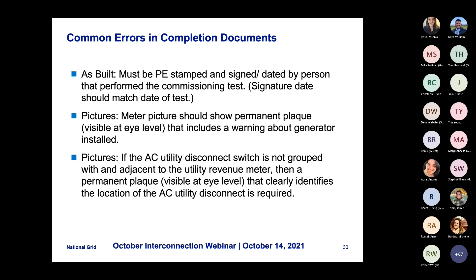For photos, we want to see a picture of the meter and showing the permanent plaque visible at eye level that includes a warning about the generator installed. Also for the AC utility disconnect switch, we want that labeled there. If it is not grouped and adjacent to the utility revenue meter, we require a placard visible at eye level that clearly identifies the location of the AC utility disconnect.